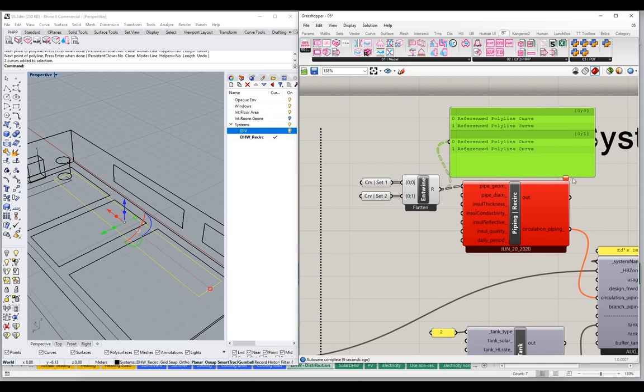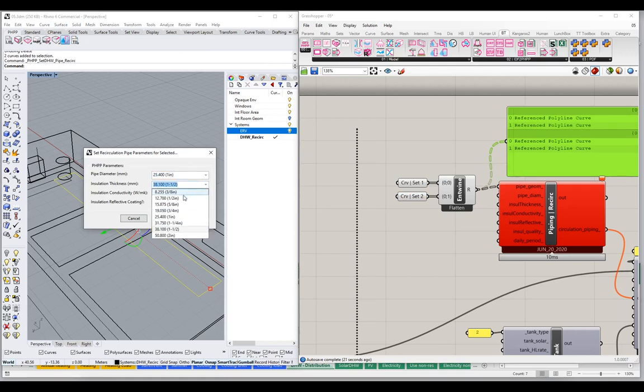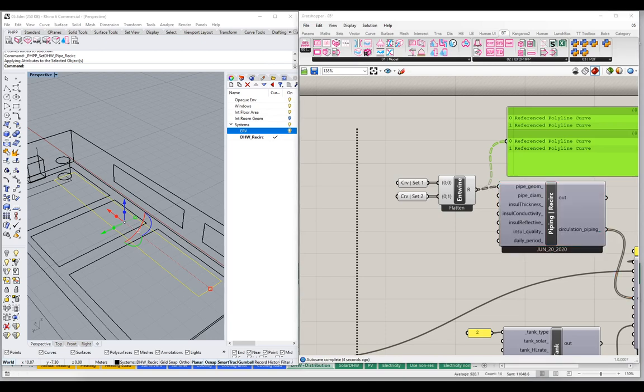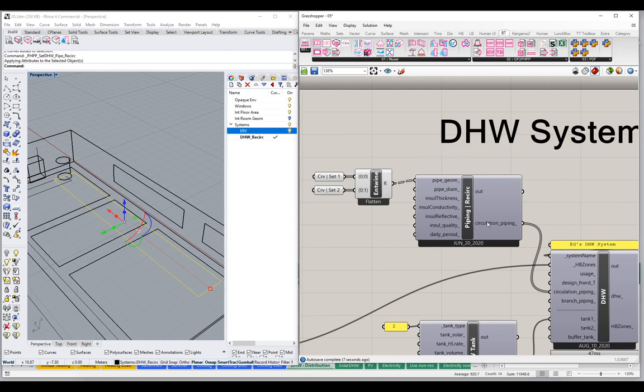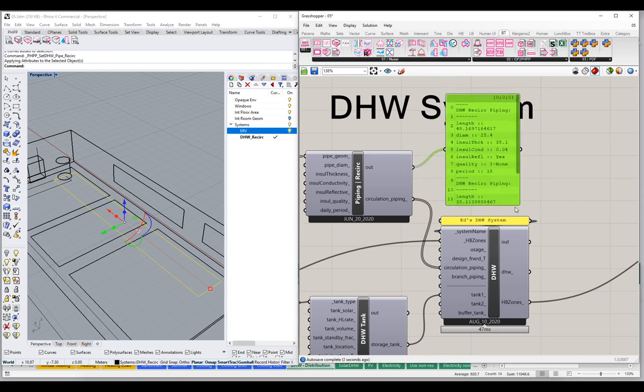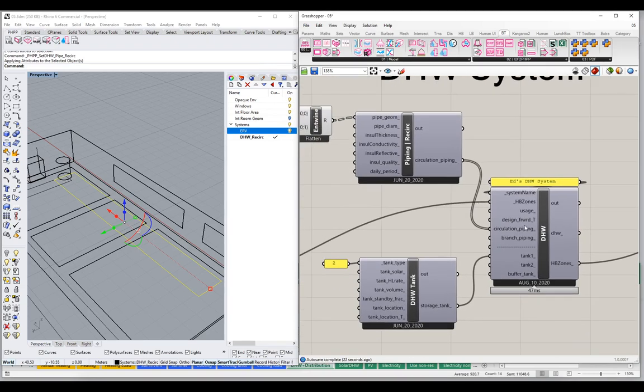We get a bit of an error because we forgot to set the parameters for the second set of curves. We need to come in here, grab those curves, and set their parameters — let's say three-quarters of an inch insulation and half-inch pipe diameter. After setting those, we're working again. Now looking at the output object, notice we actually have two domestic hot water recirc piping objects — one with a certain length, diameter, and thickness, and then a second piping object with a different length, diameter, and thickness set by those parameter values.